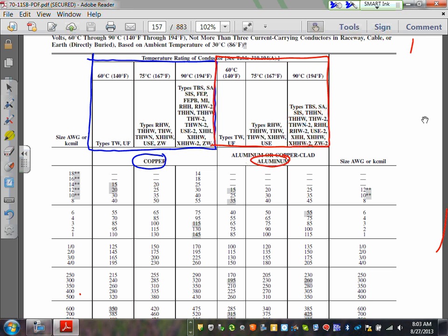The second thing, guys, applies to both sides. Let's come to the copper side. You have three options on the copper side: a 60 degree, a 75, or a 90. And each one of these options, guys, has a different ampacity for the same conductor. For example, let's take number 1 aught.